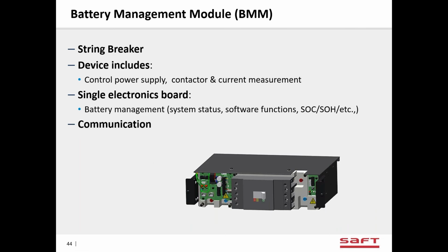The next module, the one with the breaker in it, is called the battery management module, or BMM. This has the breaker. It talks to all the modules with one communication channel, and then it talks to the master cabinet with another communication channel. This is where all the safety functions are contained. High temperature, low temperature, overcurrent, all of those that we mentioned earlier.